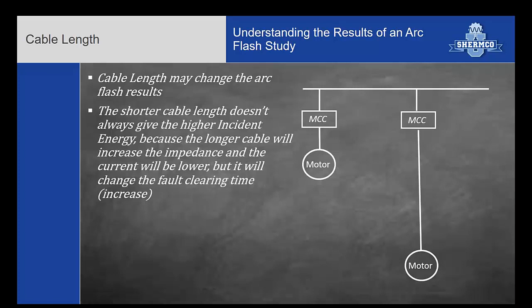And similarly, cable length and impedances matter as well. If you have two motors fed off the same MCC with identical settings, one having a 30-foot cable and one having a 300-foot cable, at which motor would the arc flash be higher? And a lot of people would automatically assume at the shorter one because you'll have more current. That's not necessarily the case because the shorter one might get into the instantaneous setting on the MCC bucket, or the longer one might be just under the instantaneous setting, and it might take a long time to trip. So impedances matter. When studies are being done, we should not just assume some minimal cable length. Cable length should be assumed within plus or minus 20%.